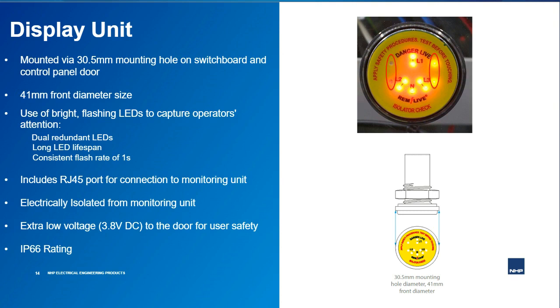The display unit has an extra low voltage value of 3.8 volts DC. Therefore, even if the user comes into direct contact with the display, they will be safe and not succumb to it.